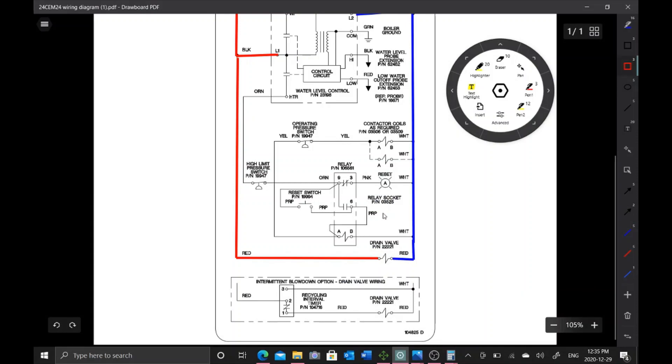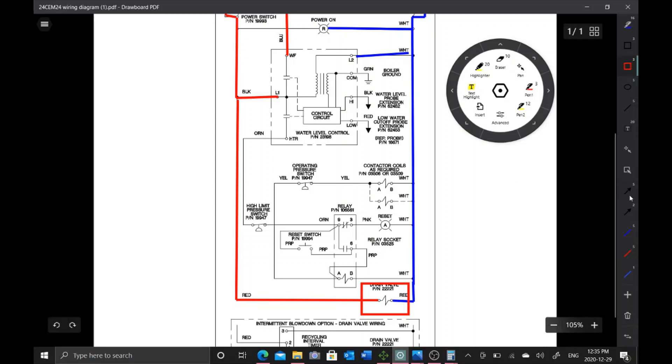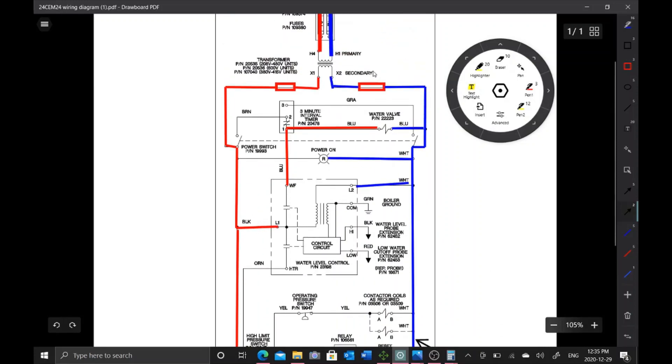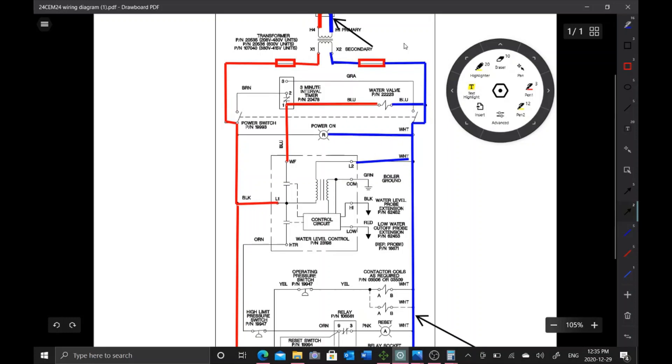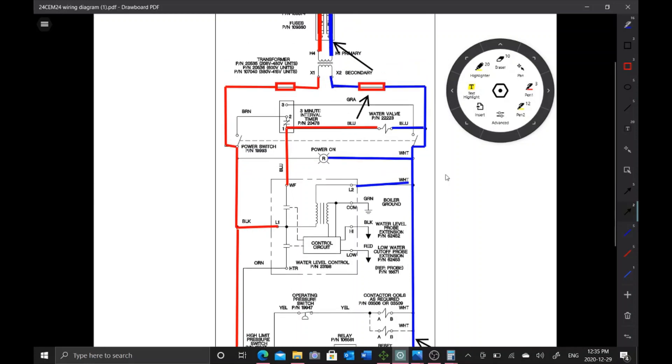Our problem here was the drain valve. It was blowing the transformer. What happens is it was drawing that 162 amps or whatever it was drawing, and it looks for the path of least resistance. In this case, it was following this line here and was taking out the transformer. How I know it was taking the neutral line is because I kept blowing this temporary fuse right here. A couple hints that I was getting that it was not a short, so I didn't look for dead shorts because I wasn't going to ohm everything out, was I was getting two seconds until it was blowing the fuse. It wasn't instantly. That was telling me like something is seized or something's drawing lots of amps. My mind was stuck on that for the troubleshooting.